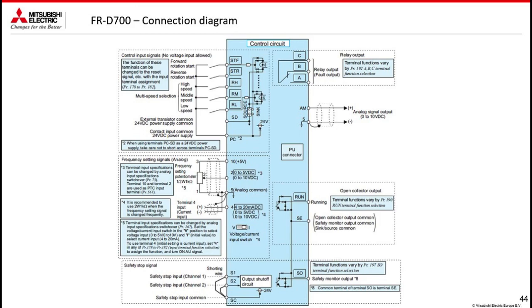Our inverters can be driven either with digital speeds or via analog references. There are two analog inputs that are the terminal 2 and the terminal 4. The terminal 2 can read from 0 to 5 volt or from 0 to 10 volt. Instead, the terminal 4, which by default is parameterized to read a current input, can be used after parameterization and moving the microswitch to voltage to read a voltage signal. The pin 10 supplies a 5 volt and the pin 5 is the common. So as if there was another additional small 5 volt power supply.